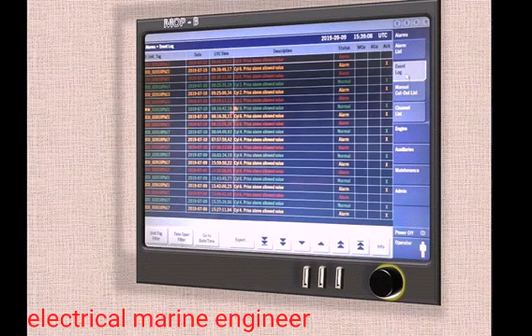Next, the alarm is the first menu. Under that sub-menu, the alarm list will show the alarms which are still activated, and the next page is the event log. The event log shows the alarms that previously occurred and were rectified or reset. The next one is the manual cutout list. If we know of a fault, like lubrication failure or some alarms, and we cut it out manually, then it will show in the list. The next one is the channel list, where everything will show: which system is connected, which sensor is connected.